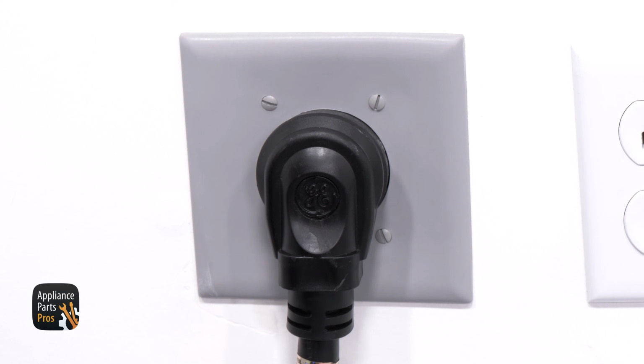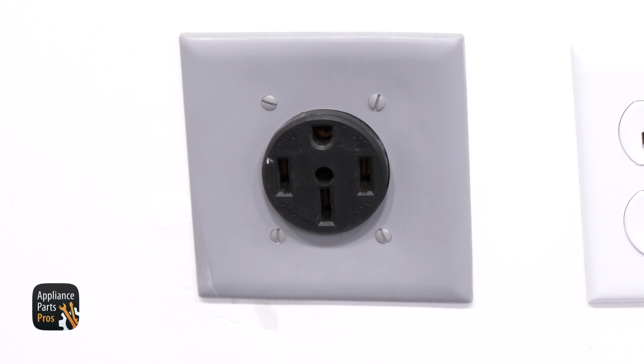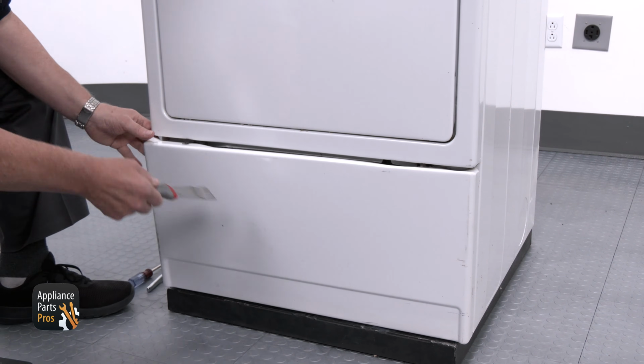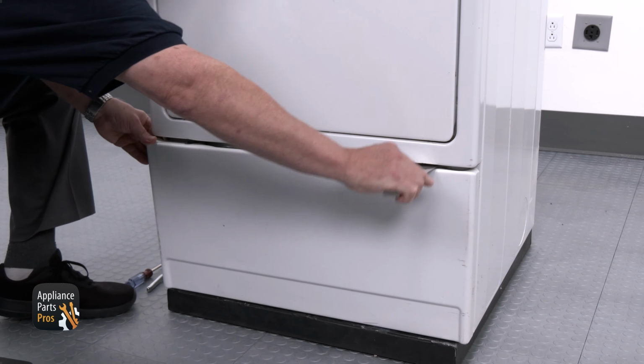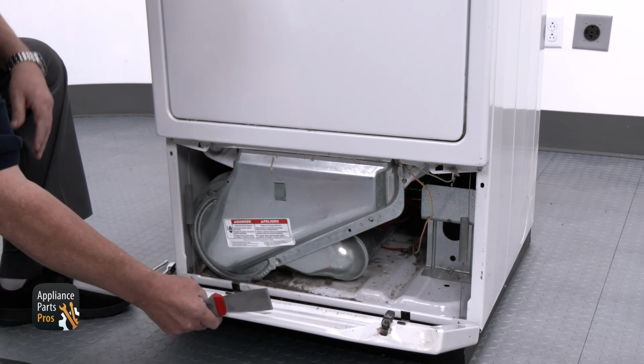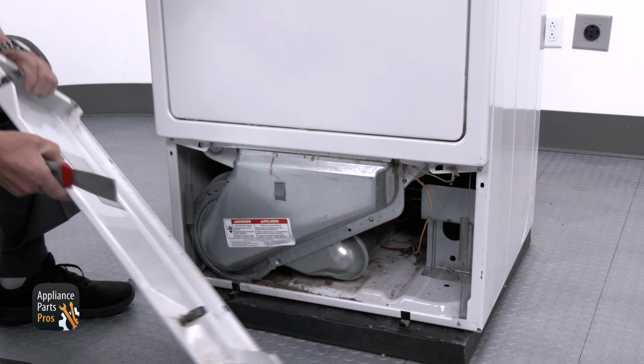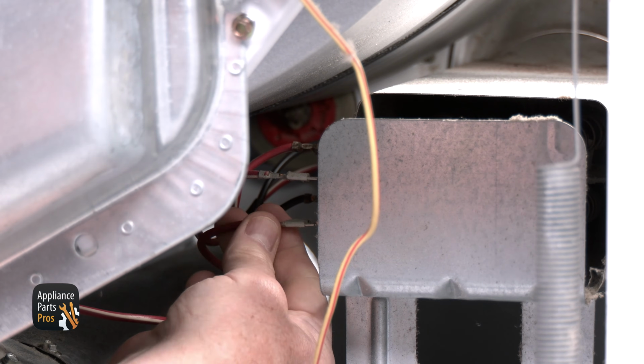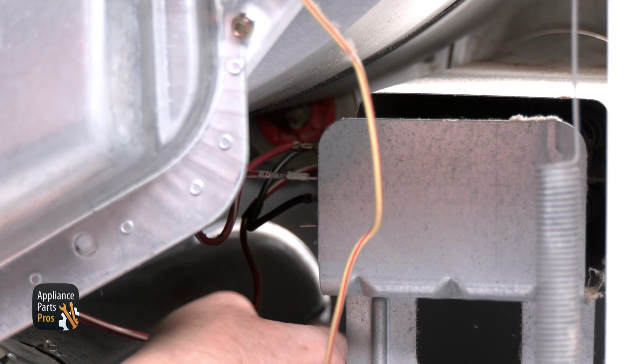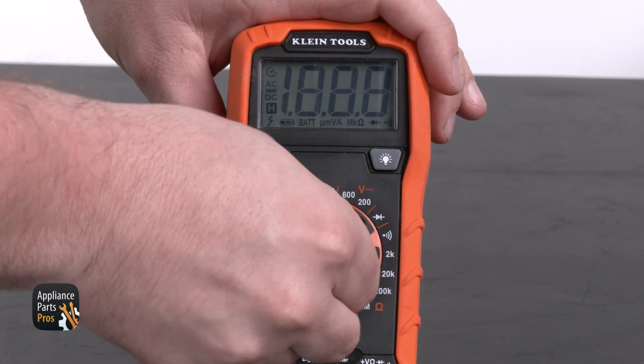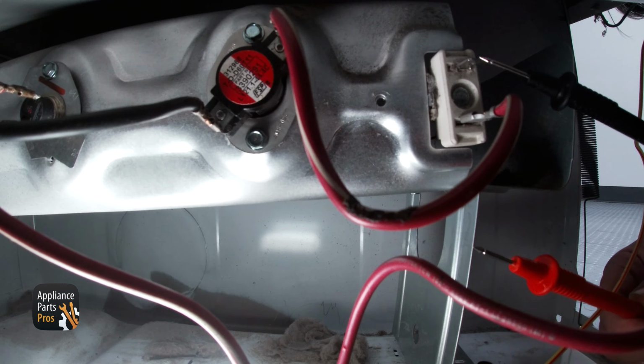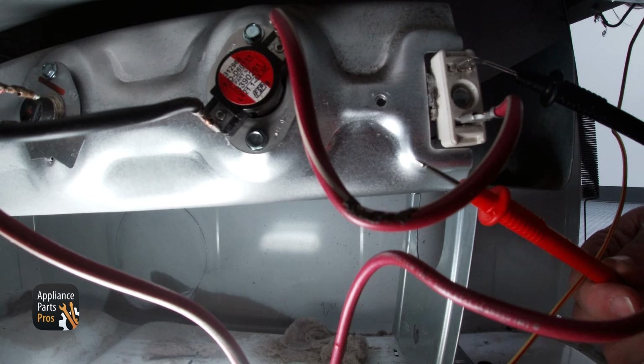Before we continue testing, make sure the dryer is unplugged from the power outlet. We need to use a putty knife and push in on the 2 clips that hold the front panel in place, then we can remove it. You also need to remove one of the 2 wires from the heating element. Now set your meter to resistance mode. Use the meter probes to check across the 2 terminals.